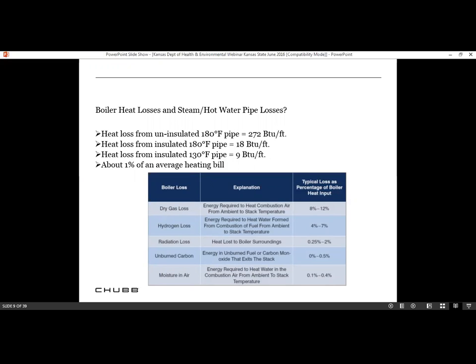Boiler heat losses and steam hot water pipe losses. If you go into a boiler plant, and I'm sure Mr. Holt's facility down there, I've been in there several years ago, but the steam piping there is insulated. But you'd be surprised, a lot of facilities do not have all their piping insulated.